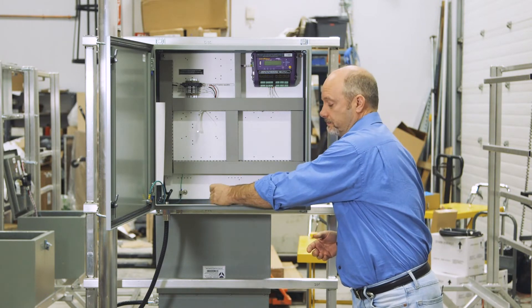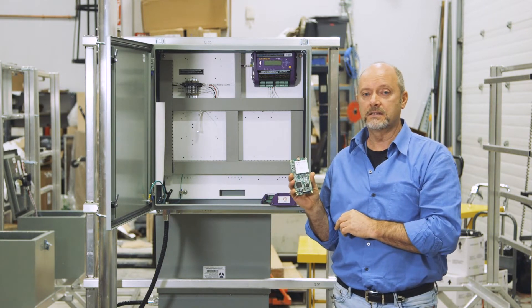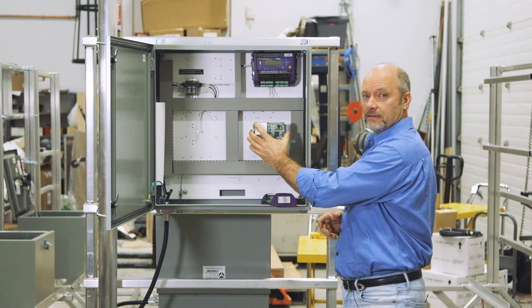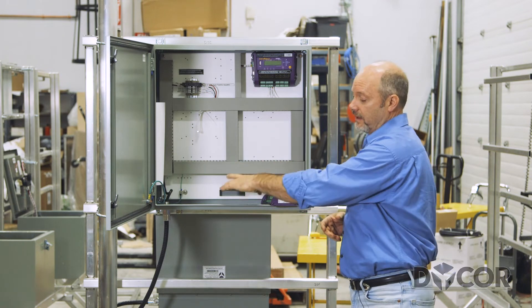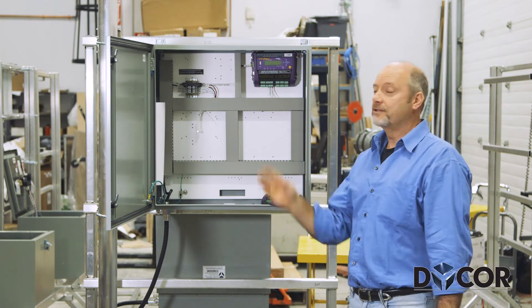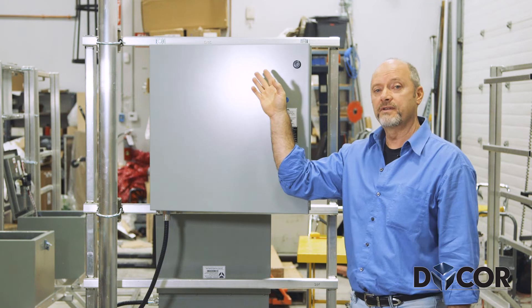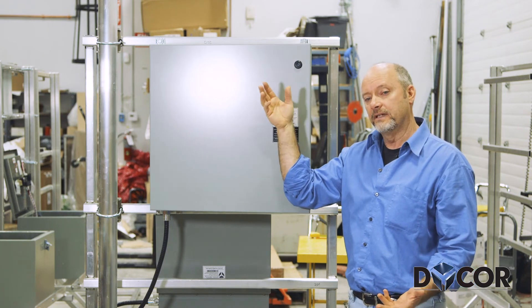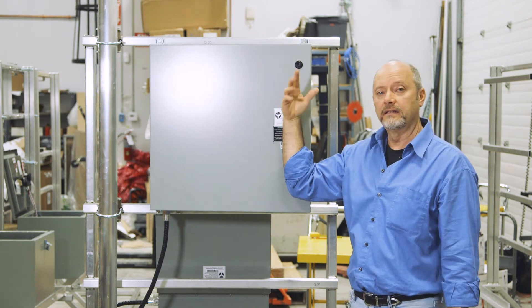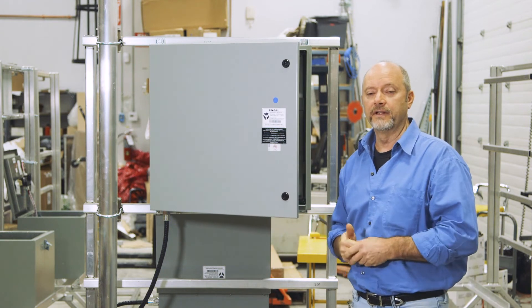We also have a board level radio — it's a 900 megahertz FreeWave radio — and this is mounted in the cabinet here, wired up with an antenna power source, so it becomes part of a network. Also part of the panel is an aluminum mast which can go up to 35 feet. You mount a Yagi antenna on there with your solar panels a little bit lower down, and you have 35 feet of clearance from the ground to have your network connectivity.